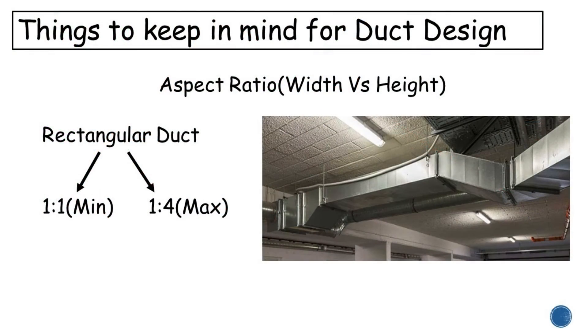Another important consideration is the aspect ratio of the rectangular duct. The maximum allowed aspect ratio is 1 to 4. For example, if your duct height is 200 mm, the width of the duct should not exceed 800 mm. This ratio plays a major role in duct sizing.